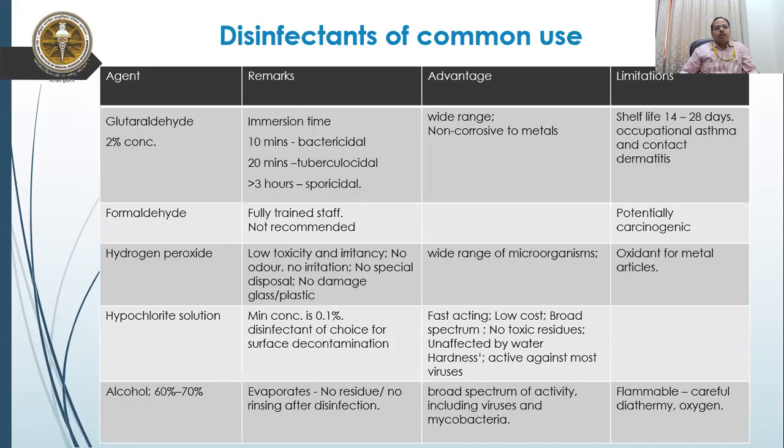which we use. Let's say glutaraldehyde 2%. Commonly we call it Cidex. We have been hearing that since our MD days. This 2% glutaraldehyde, if you want to use it for your equipment and instruments, the minimum immersion time is 10 minutes if you want to kill bacteria. If you want to kill bacteria as well as tubercular bacteria, then you need to keep it immersed for at least 20 minutes.